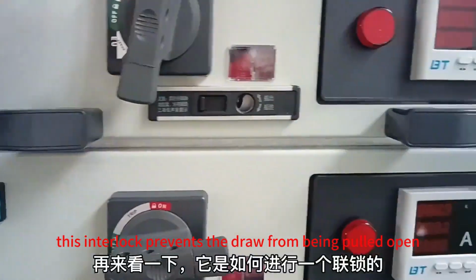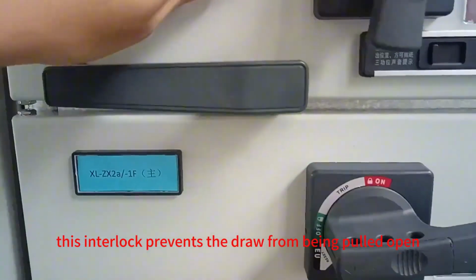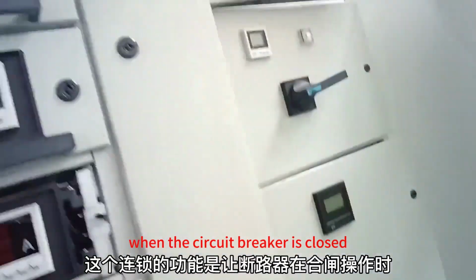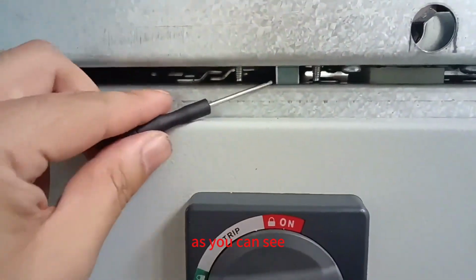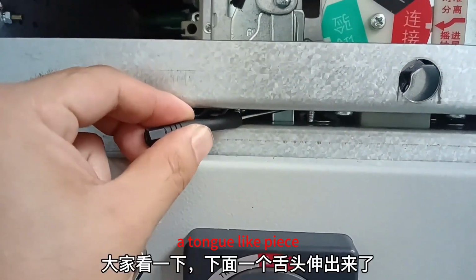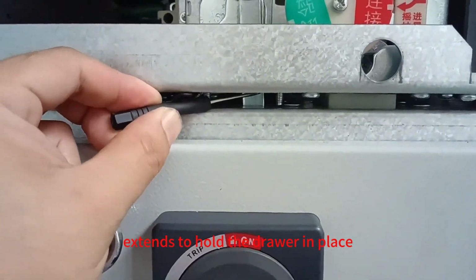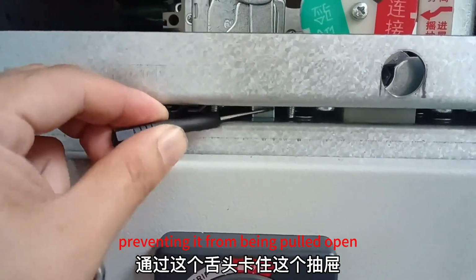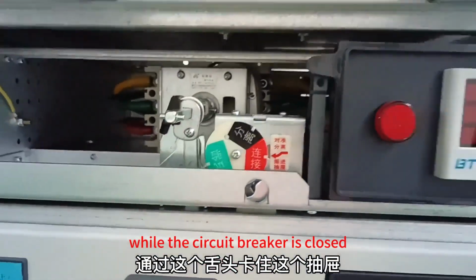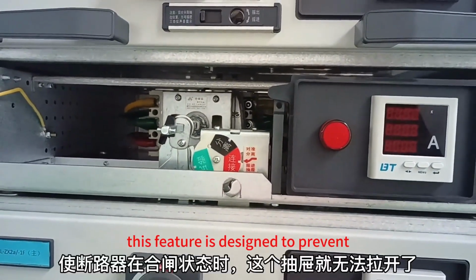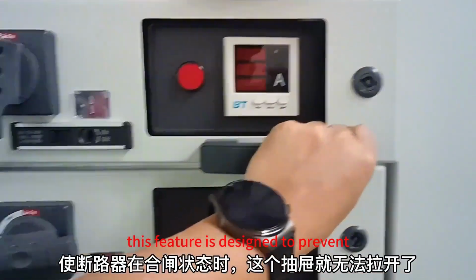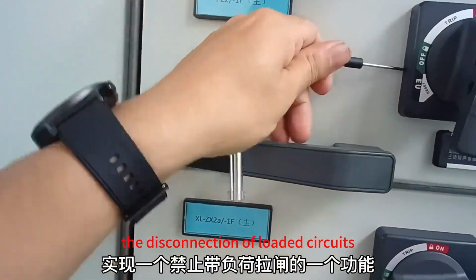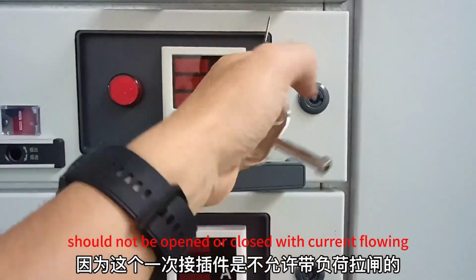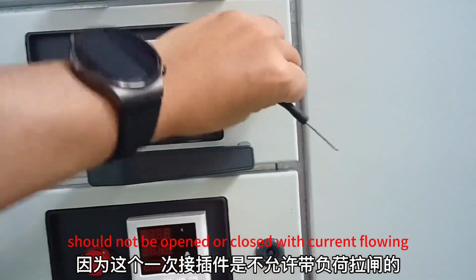This interlock prevents the drawer from being pulled open when the circuit breaker is closed. As you can see, a tongue-like piece extends to hold the drawer in place, preventing it from being pulled open while the circuit breaker is closed. This feature is designed to prevent the disconnection of loaded circuits, as the plug-in connection should not be opened or closed with current flowing. That's it for this video.